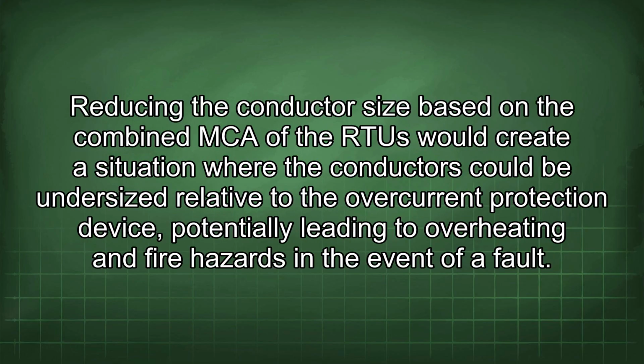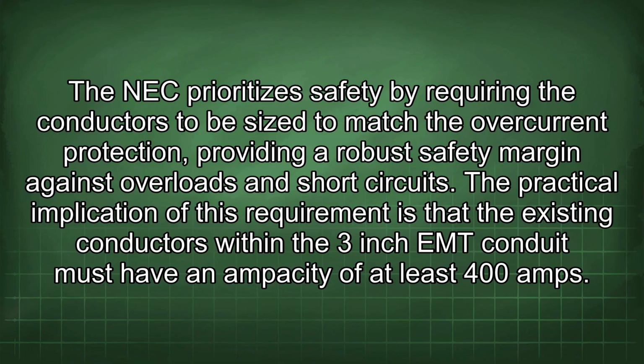Reducing the conductor size based on the combined MCA of the RTUs would create a situation where the conductors could be undersized relative to the overcurrent protection device, potentially leading to overheating and fire hazards in the event of a fault. The NEC prioritizes safety by requiring the conductors to be sized to match the overcurrent protection, providing a robust safety margin against overloads and short circuits. The practical implication of this requirement is that the existing conductors within the 3-inch conduit must have an ampacity of at least 400 amps.